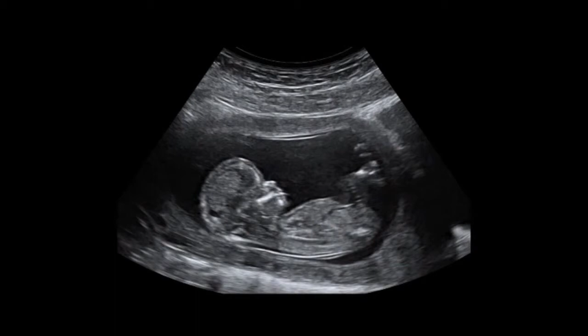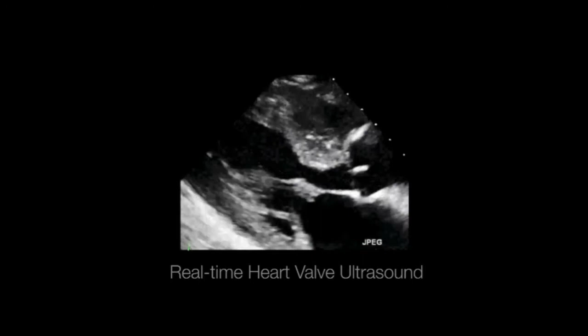This electric pulse is then sent to the computer display. The computer calculates the time taken by the electrical pulse to make the round trip into the body and back, and determines where on the display, at what depth, a dot is projected. The intensity of the reflected echo determines what shade of gray, from light to dark.